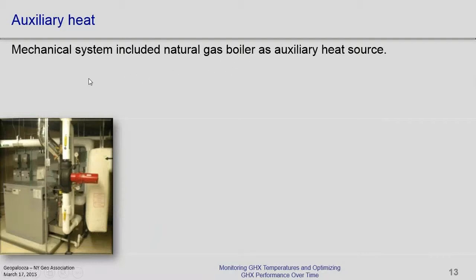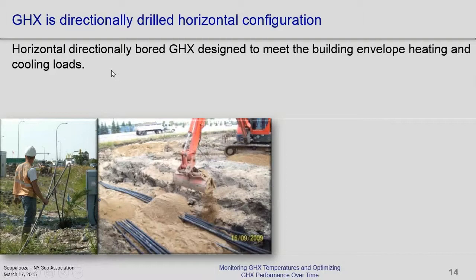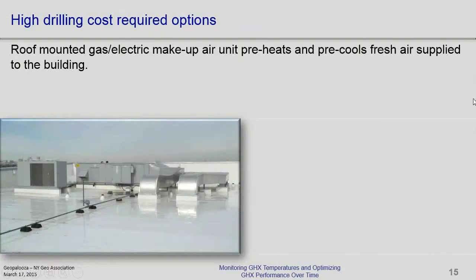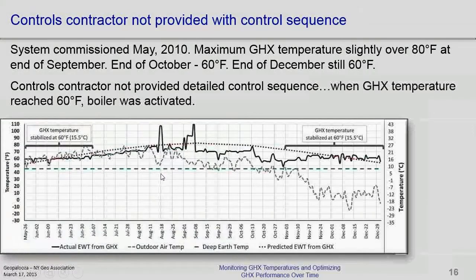So with horizontal directional drilling, I think we've got about 72 horizontal boreholes that are just under 300 feet long and connected to the building. They've got a gas-fired makeup air unit that supplies fresh air to the building, and it also pre-cools the fresh air to the building. So the system was commissioned in May of 2010, and the temperature was slightly over 80 degrees by about the end of September, right around here.